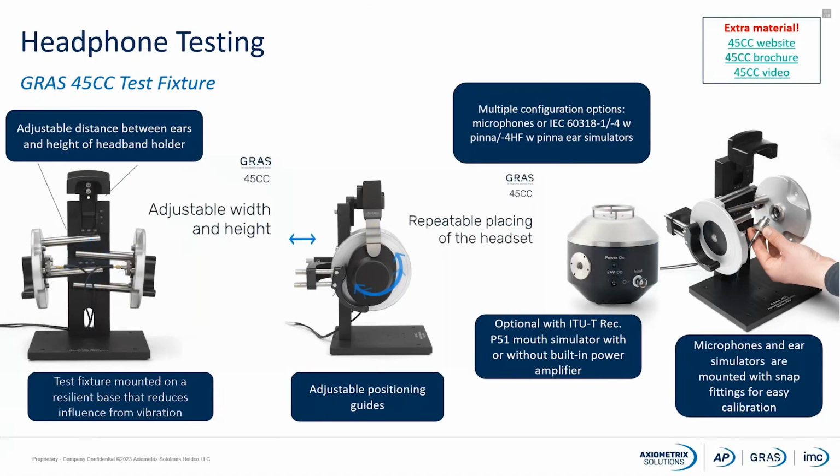It is easy to remove the microphones or ear simulators, as these have been mounted with a special snap fitting system, so it's easy to dismount and mount these again, for instance when you are doing calibrations and validation of the microphones or ear simulators used for the fixture.